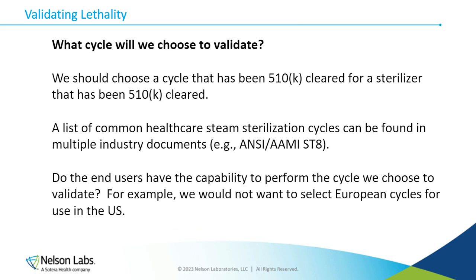The first step is choosing which cycle to validate. We should choose a cycle — and a sterilizer — that has been 510(k) cleared. We can look at industry documents like ANSI/AAMI ST8 or the FDA guidance document if we need help deciding the cycle to validate. We also need to understand whether our end users have the capability to perform the cycle we choose — for example, we would not want to validate selected European cycles for use in the US.